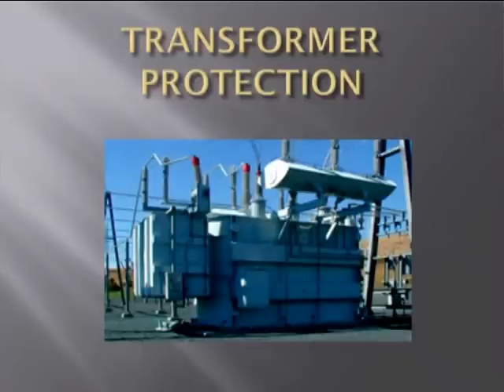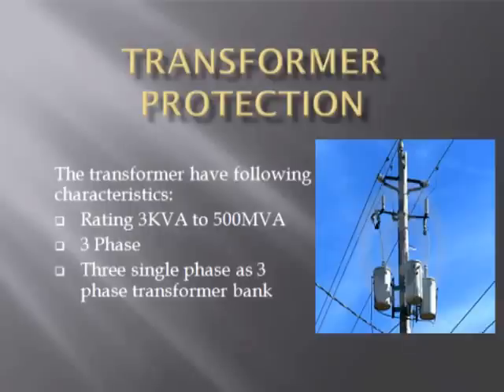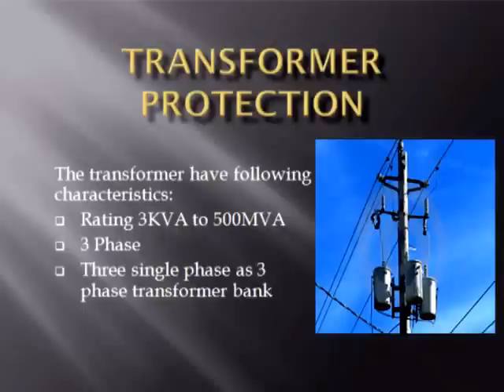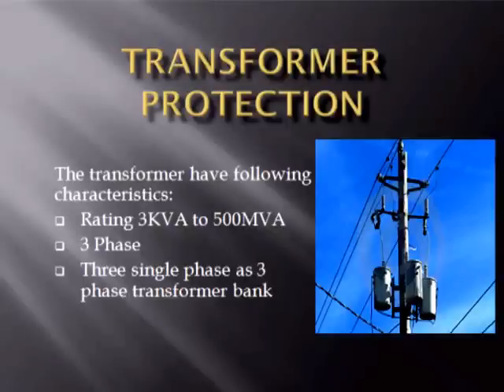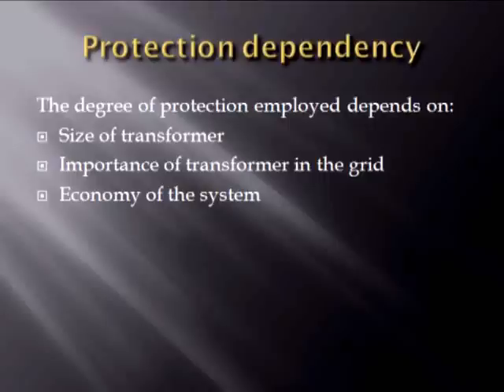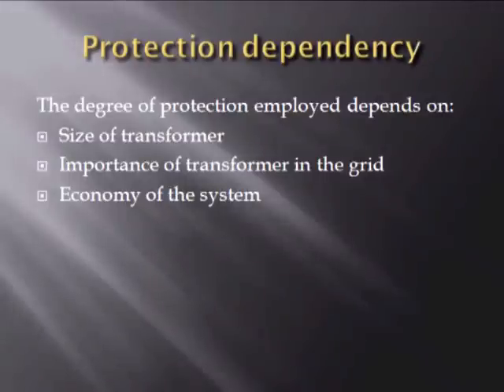Now we will talk about transformer protection. The transformers used in the system have a rating of 3 kVA to 500 MVA and they can be three-phase or can be three single-phase transformers connected as three-phase transformer banks. These transformers are connected in delta or Y connection schemes according to the required voltage or current levels. Y-delta transformers have a phase difference of 30 degrees according to IEEE standards. The degree of protection employed for a particular transformer depends upon its size, its importance in the system, and the economy of the design. Sometimes circuit breakers are omitted to make the design less expensive, but appropriate amendments must be made to the design for protection.